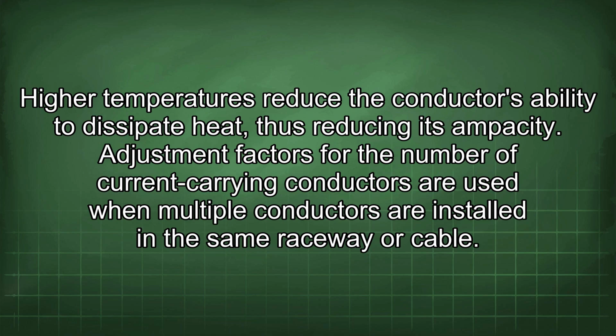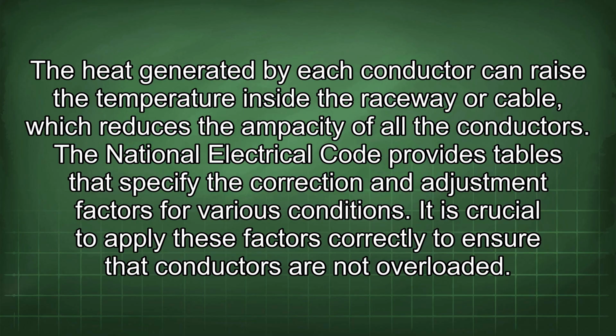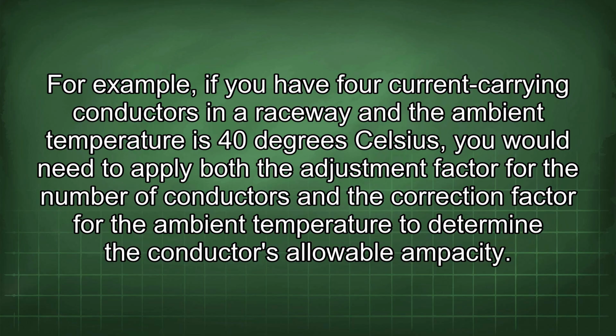Adjustment factors for the number of current-carrying conductors are used when multiple conductors are installed in the same raceway or cable. The heat generated by each conductor can raise the temperature inside the raceway or cable, which reduces the ampacity of all the conductors. The National Electrical Code provides tables that specify the correction and adjustment factors for various conditions. It is crucial to apply these factors correctly to ensure that conductors are not overloaded. For example, if you have 4 current-carrying conductors in a raceway and the ambient temperature is 40 degrees Celsius, you would need to apply both the adjustment factor for the number of conductors and the correction factor for the ambient temperature to determine the conductor's allowable ampacity.